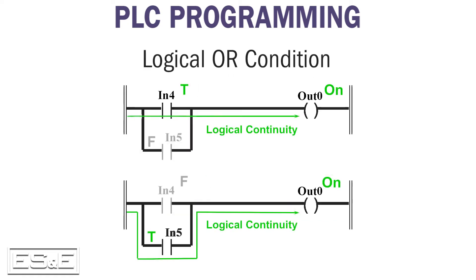These rungs show the logical OR condition. In the top rung, input four is true, so the result is true and the output is on. Input five is off, but it has no effect on logical continuity because the PLC scans from left to right, top to bottom. Conversely, the lower rung shows input four as false, so the scan drops to the branch containing input five. Because input five is true, the rung solves true, and the output is on. Once again, the scan is left to right, top to bottom.